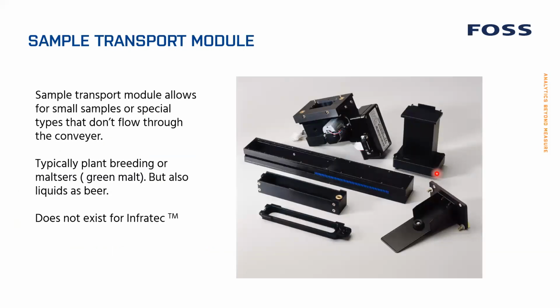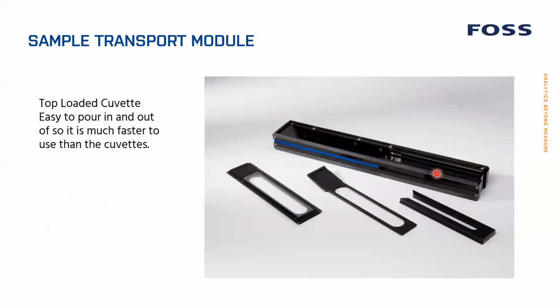The sample transport module is for those who want to run special samples, small sample volumes, or special sample types that don't flow through the conveyor. This would typically be plant breeding or maltsters, or if you want to do a liquid. This does not exist for the Infratec TM. So this is one of the things that differs the Infratec TM from the Infratec Nova. Anyone who wants to use this needs to have an Infratec Nova or a 1241.